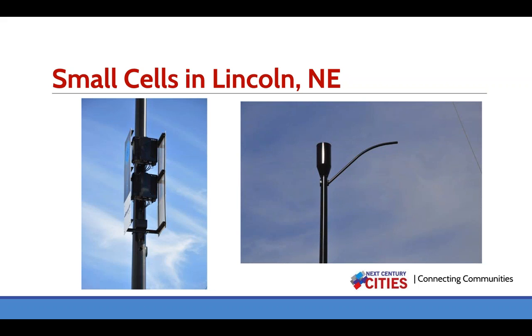Yeah, I think to David's point, it really comes down to structural capacity, and we run structurals on everything anyway, just from a liability perspective, whether it is attaching to an existing wood electrical standard utility pole, a street light pole, whatever it happens to be. And to his point, we do find the majority probably need to be replaced, because these were put up a while ago, and especially direct burial wood poles, a lot of them just weren't designed to handle the amount of loading, for wind loading or just sheer weight loading. So we replace poles all the time, and again, everything from direct burial wood poles to custom design poles in various situations.